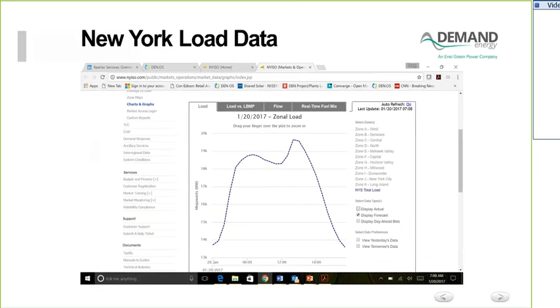It worked so well that it taught us we don't just have a statewide peak like one of the slides showed. A lot of people might think your building peak is more or less similar to that, but it really isn't. The building peaks many times during the day, dozens upon dozens of times. So there's savings that can be driven there without chopping down that whole big mountain. Commercial buildings ramp up kind of linearly, stay flat, then go down. This is the opposite of a residential building, where you have a different kind of movement of people and usage of power. We found that small things going on in the building during the day could create peaks significant enough to be dealt with by injecting power from the system.